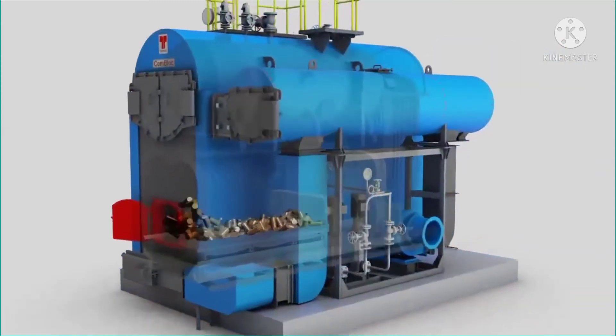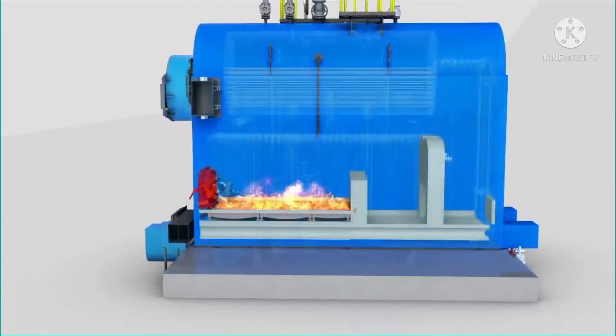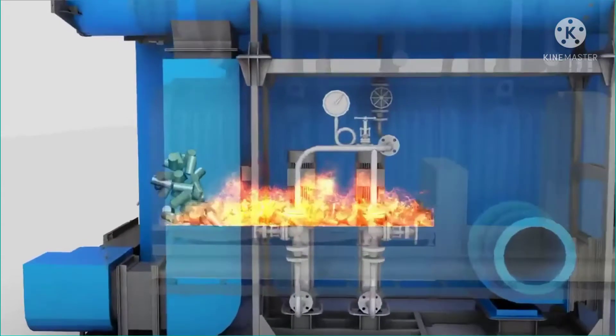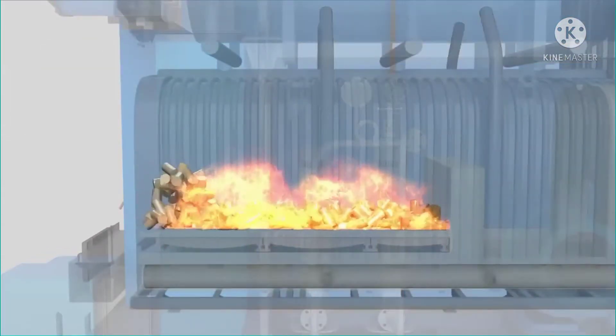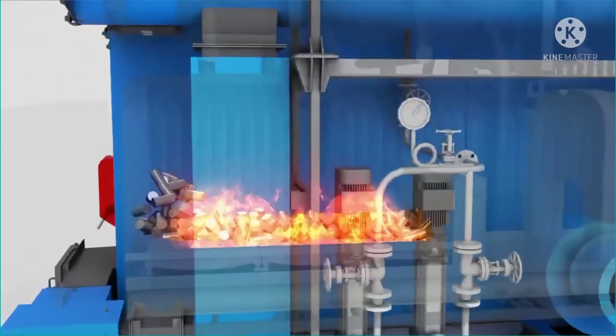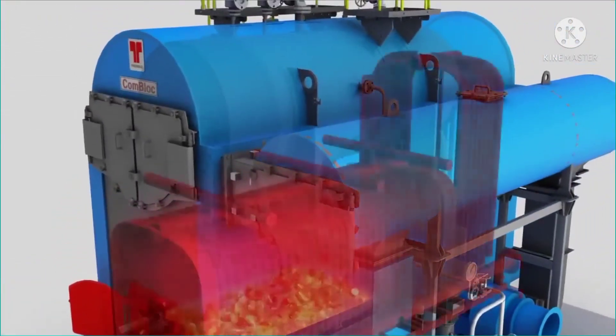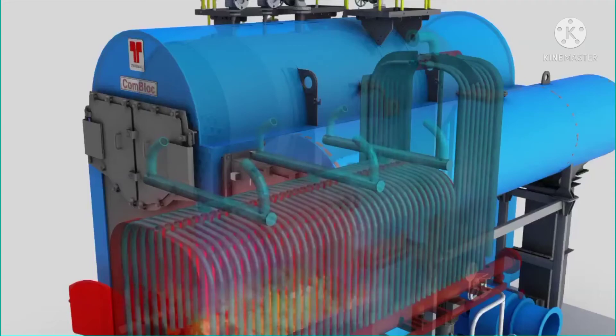Once inside the combustion chamber, the fuel is ignited and combustion starts. Around the combustion chamber is the membrane panel, which carries water through it. The downcomers pass the water from the boiler drum to the bottom headers of the membrane panel. Due to the heat from the combustion chamber, the water gets heated and a mixture of steam and water exits the membrane panel through the risers into the steam drum.